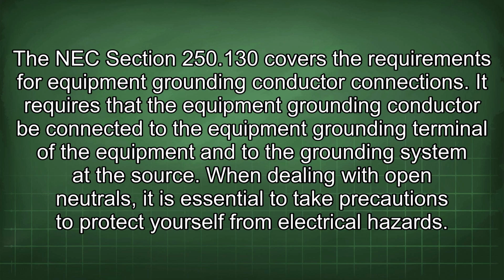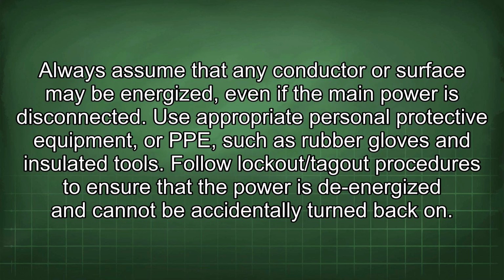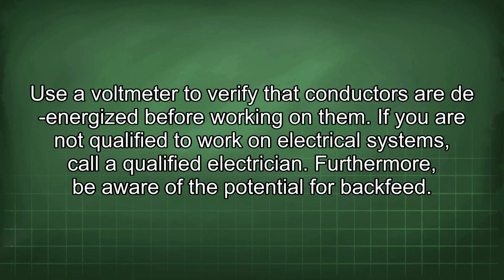The NEC Section 250.130 covers the requirements for equipment grounding conductor connections. It requires that the equipment grounding conductor be connected to the equipment grounding terminal of the equipment and to the grounding system at the source. When dealing with open neutrals, it is essential to take precautions to protect yourself from electrical hazards. Always assume that any conductor or surface may be energized even if the main power is disconnected. Use appropriate personal protective equipment, or PPE, such as rubber gloves and insulated tools. Follow lockout/tagout procedures to ensure that the power is de-energized and cannot be accidentally turned back on. Use a voltmeter to verify that conductors are de-energized before working on them. If you are not qualified to work on electrical systems, call a qualified electrician.